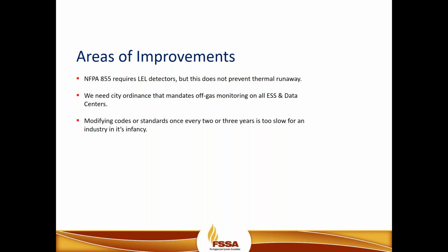So as we look for areas of improvements, we look towards the codes and standards. NFPA 855 is now requiring LEL detectors. However, the LEL detectors are not there to prevent thermal runaway. However, to identify possible methane or explosive type environment for first responders. We need city ordinances and mandates for off-gas monitoring in all energy storage systems, power generation facilities, and data centers. Modifying the codes and standards once every 2 or 3 years is not addressing the issue quickly enough. We need to be able to adopt technology and work to identify the risk from a performance-based standard, not just a prescriptive-based standard.